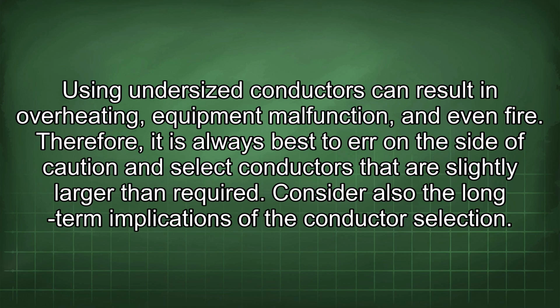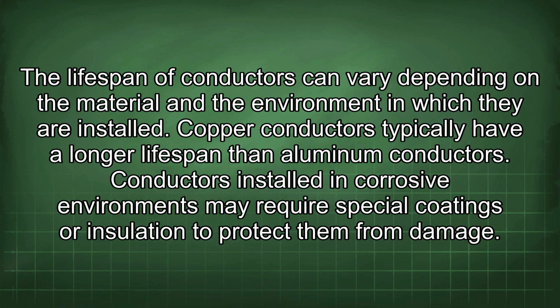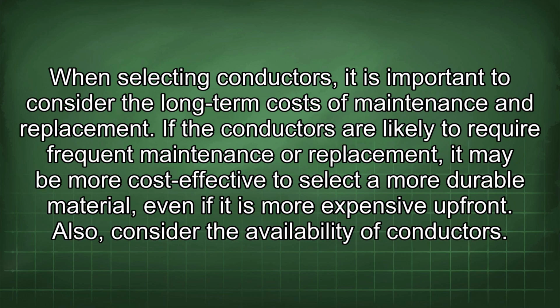Consider also the long-term implications of the conductor selection. The lifespan of conductors can vary depending on the material and the environment in which they are installed. Copper conductors typically have a longer lifespan than aluminum conductors. Conductors installed in corrosive environments may require special coatings or insulation to protect them from damage. When selecting conductors, it is important to consider the long-term costs of maintenance and replacement. If the conductors are likely to require frequent maintenance or replacement, it may be more cost-effective to select a more durable material, even if it is more expensive upfront.